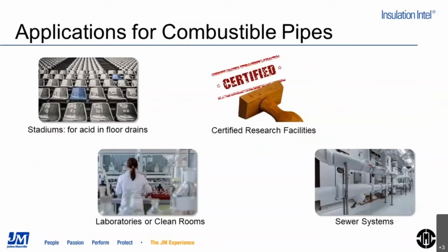The first one was a stadium here in Minnesota where they ran a green pipe for acid waste, for cleaning kitchen floors and degreasing. But all the air handling units, the rooms themselves, were return plenums, and that's where a lot of these drains were. So the fire inspector for the city would not allow them to do that. So we, with JM's help, came up with the rating. We got the letters, they did the testing, and we could insulate it with the HP, fittings included, on this job. So we did that.